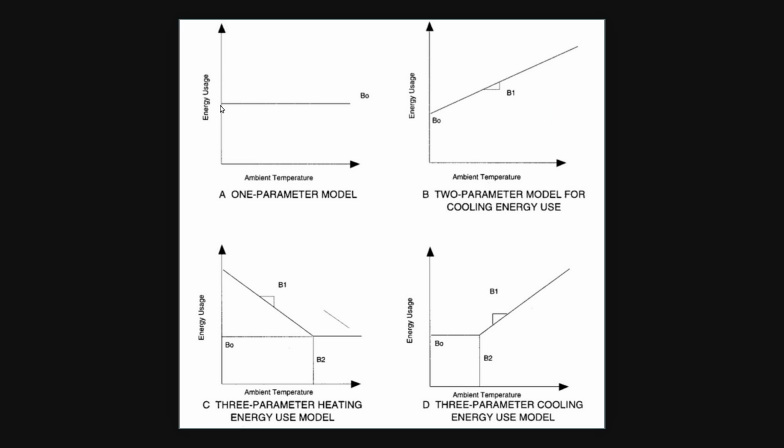For example, if the building had no correlation, as it got warmer it did not require more energy, you would see a flat characterization equation. Or, for example, as the average temperature increases on this regression model, you would see an increase of energy use. So this is, of course, talking about air conditioning within a building.